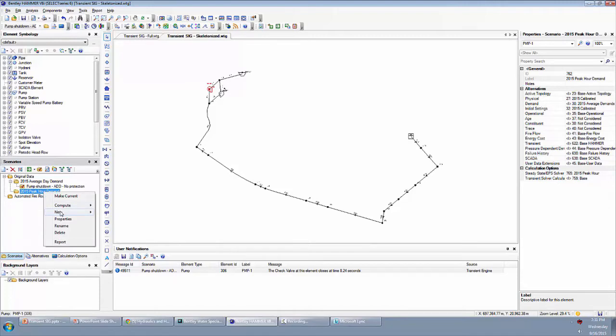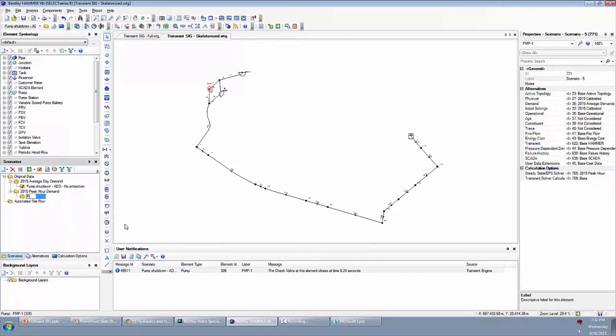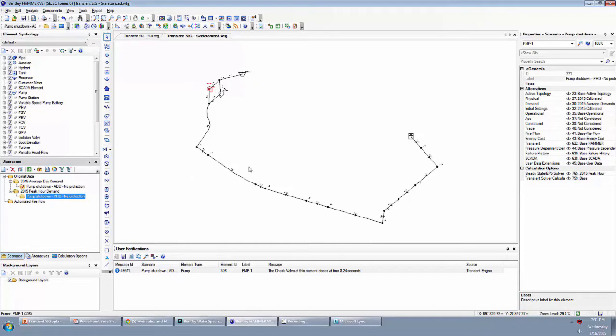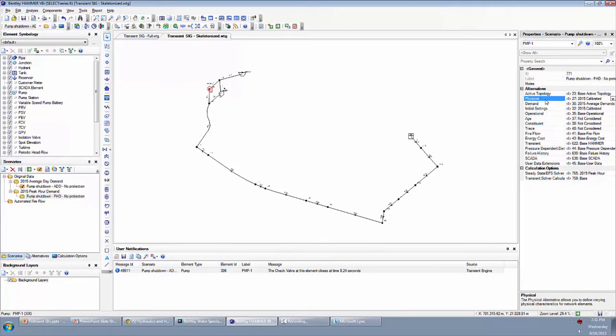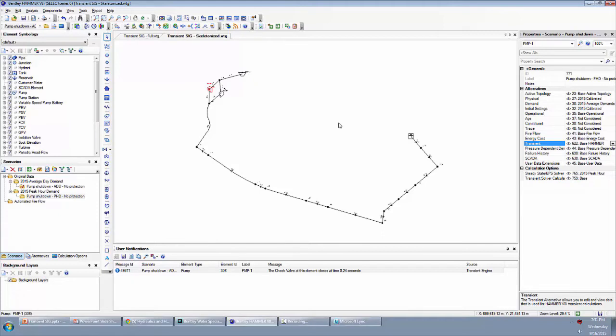So what I can do is create a new child scenario and I'll call this pump shutdown peak hour demand, no protection. So what we want to do here is choose the corresponding alternative. Your alternatives are basically where your data is stored, the different categories. For example, a physical alternative stores any physical data, transient alternative stores any transient specific data like those things that we saw in the transient section of your various element properties.